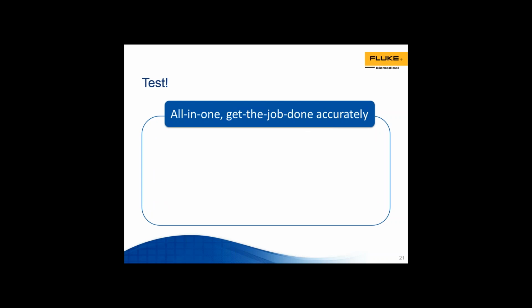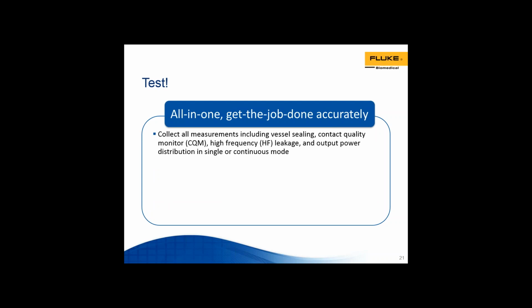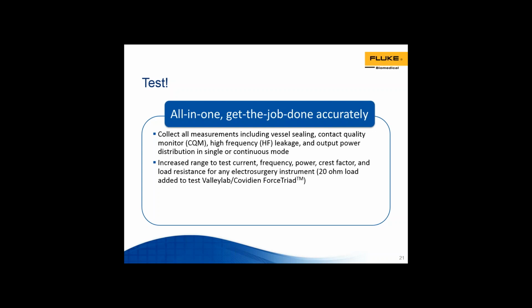And finally, coming down to the capability of the product in terms of features and functions, this is an all-in-one analyzer, and the focus has really been on accuracy and quality. So the QA-ES3 is capable of collecting all measurements, including vessel sealing, contact quality monitor, also known as CQM, high-frequency leakage, and output power distribution in single or continuous mode. We have increased the range to test current, frequency, power, crest factor, and load resistance for any electrosurgery instrument. In fact, with this product, we've added an additional load, so it has the ability to test the ForceTriad.